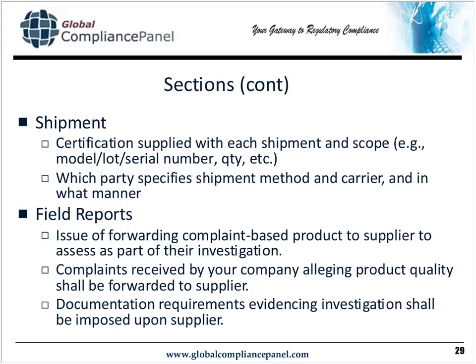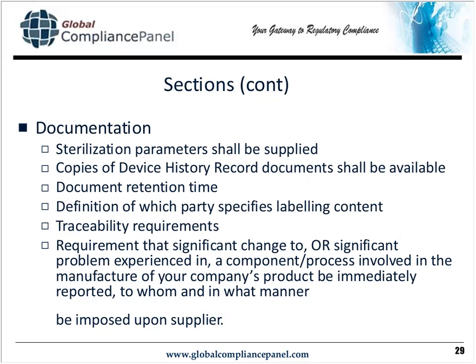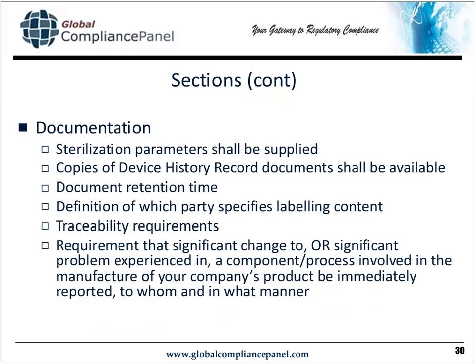That you do receive complaints from the field, and you do perform investigations on that product. And you want to let them know that if your investigation at least suggests, if not concludes, that their product is an issue, you're going to be issuing them some documentation for their completion, which requires them to do a root cause analysis of the component that was at issue. You'd be surprised how many suppliers are unaware that that's what we do.